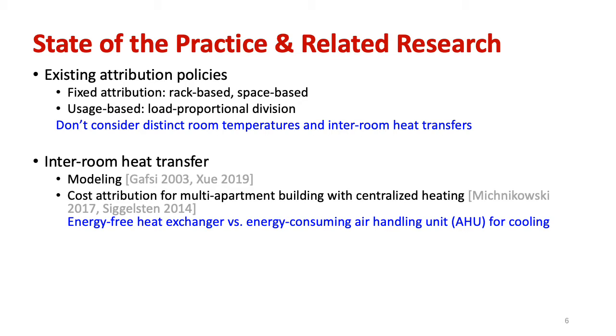There are existing studies on inter-room heat transfers. Some focus on modeling the heat transfers. There are 2 studies addressing the heat transfers for cost attribution in a multi-apartment building with centralized heating. The in-room heat exchangers in the heating system do not consume energy. Differently, the in-room air handling units in the data center cooling system consume energy. As a result, addressing the heat transfer problem for data centers is more challenging than for the building heating systems.